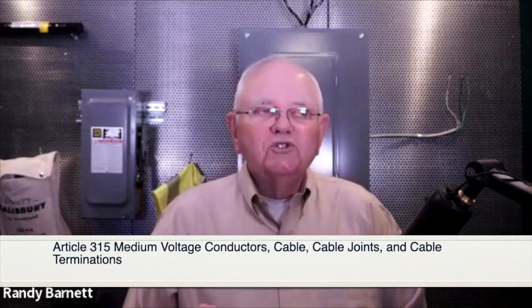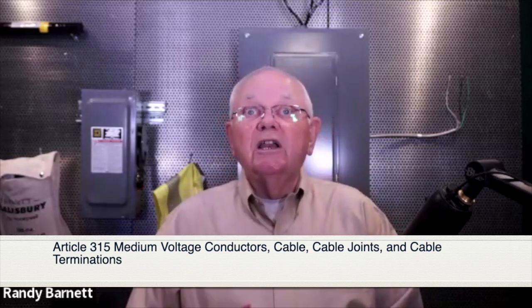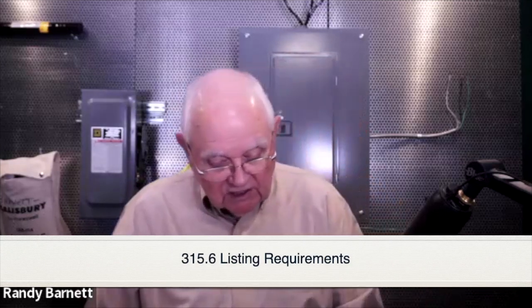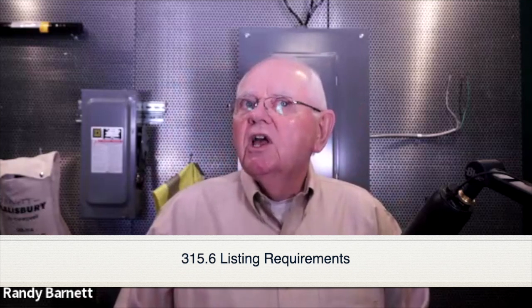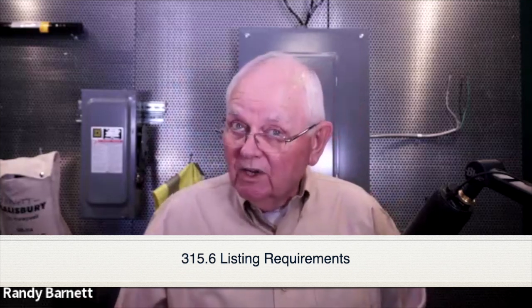Cable joints, you and I would probably call splices, but for some terminology reasons, they use the term cable joints in Article 315. Everything's required to be listed. So this cable has to be listed by a nationally recognized testing laboratory, which we'll find out when we read the information on here. Pretty small, huh? I'll read it to you, and we're going to find out that yes, this cable is listed. As far as the cable joints and cable terminations, those don't have to be listed until January 1st, 2026. With the next code edition, it's not terribly uncommon to see something like that, where we don't have products that meet the UL listing requirements yet, but they certainly expect it to be available for the next edition of the code. So it gives us a little heads up there.